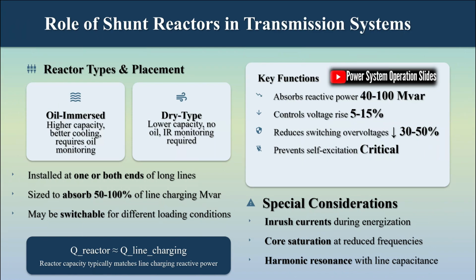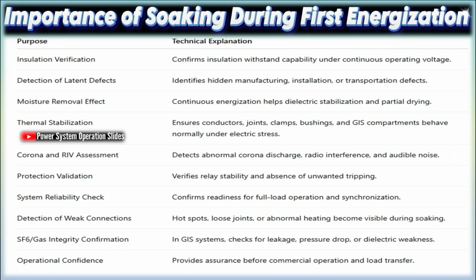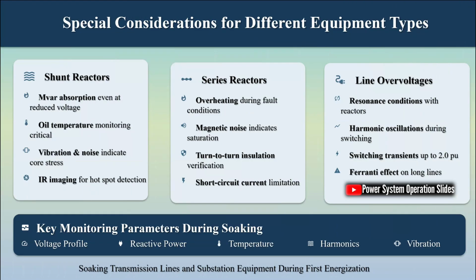Rather, it serves as a controlled validation process that allows engineers to observe how the insulation system and associated components behave under electrical stress. During manufacturing, transportation, storage, installation, and construction activities, equipment may be exposed to mechanical shocks, moisture ingress, contamination, or environmental conditions that can negatively affect insulation performance.